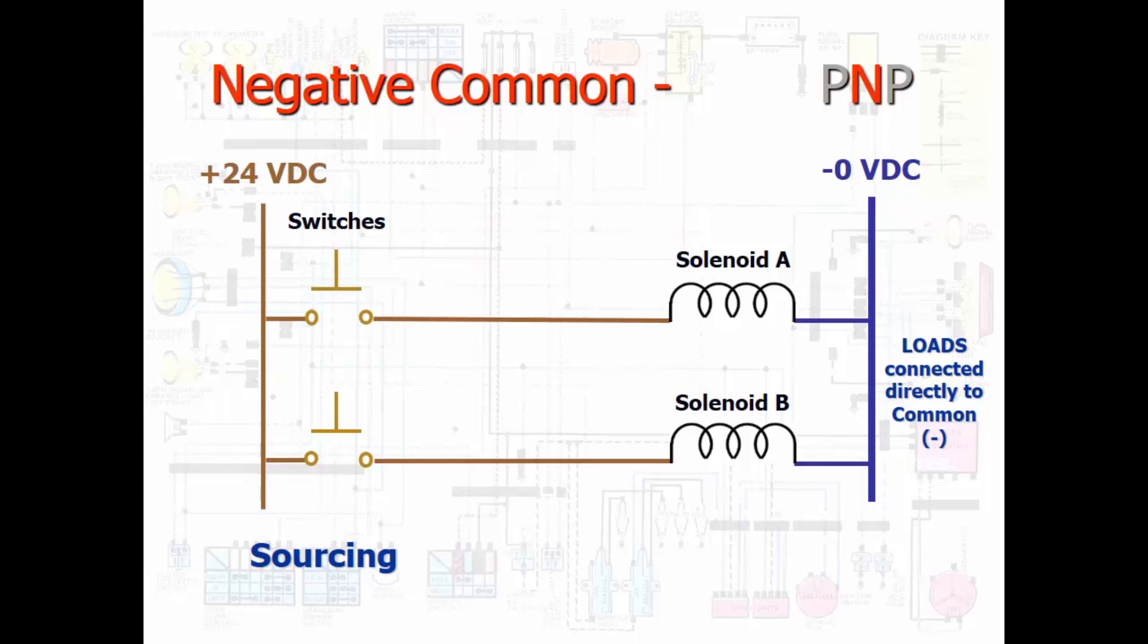If the solenoids are PNP, they would be attached to the negative common as shown here. The valve needs controller signals to close the switches for either solenoid A or B to be turned on.